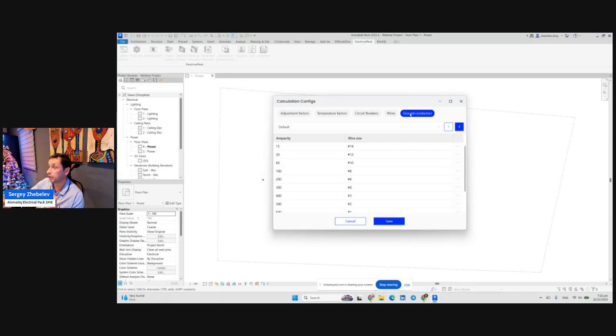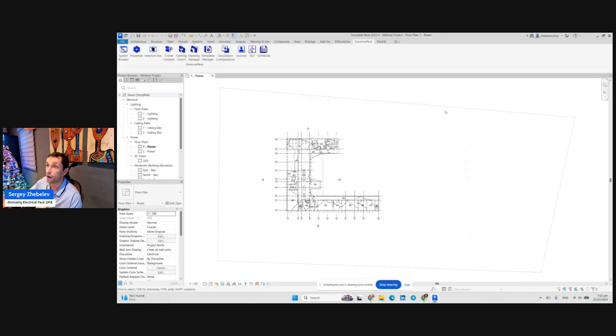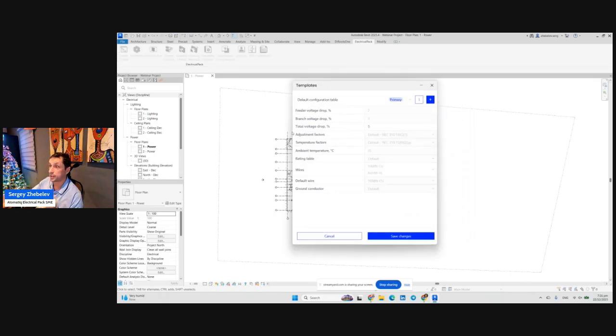These are settings, and all these settings go through the templates manager. What is the templates manager? It's the place where you set up all your settings: adjustment factors, temperature factor, ambient temperature as default, and the wires you're choosing in your project. You're adding wires, choosing default wire, and you can create as many templates as you need. Our idea is to share this template across project members, because it's not comfortable to redo it every time when working on a common project.